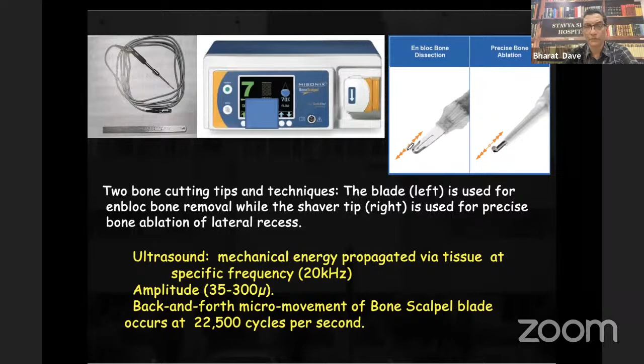Now you must remember this and watch this. This setting is the frequency. 100% is the pulse, so if you keep it at 100%, it will cut all the time. If you keep it at 80-10 or 80-20, then it will have pulsed cutting. And the flow: when you are operating a fluorotic case, you should use 100% flow. Otherwise, you can keep it around 70% flow. You can increase and decrease this depending upon the bone density. If you increase it to 10, you will have a stronger cutting edge. So this is a must.